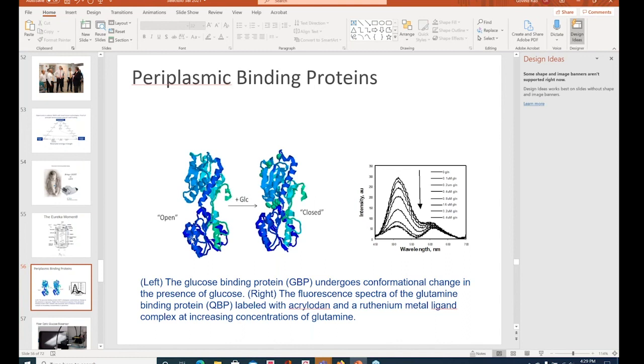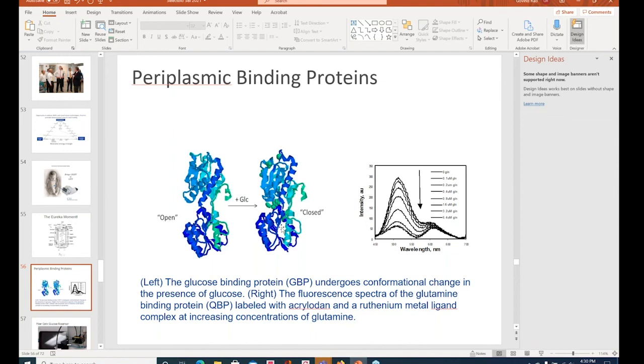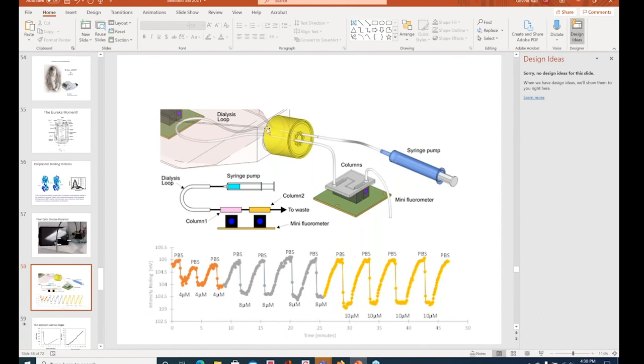These are E. coli and many other, they're called the ABC transporter proteins. Mother nature evolved them over millions of years to help move glucose and other substrates into the cell. If you look at the open and closed configuration, imagine picking up a peanut with your index finger and your thumb. That's what's happening. So when glucose is bound, there's a conformational change. And if you put a fluorophore anywhere on this molecule, the local environment around the fluorophore changes, and you get micromolar sensitivity. So it's 1,000 times more sensitive than glucose oxidase. And because it's not an enzymatic conversion, it's a reagentless sensor. It's completely reversible. So we built the instrumentation for it. And we've got sensors that can go in as a dialysis loop into just about any bioreactor and measure glucose and glutamine.